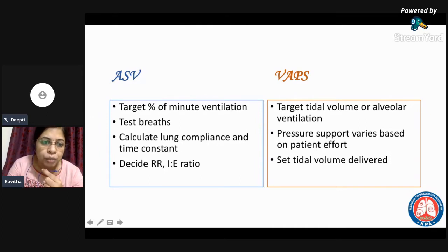But in a patient where you need to make sure that the patient is getting enough tidal volume, which are these conditions, we'll see in the future slides. But in a patient where you want to ascertain that a particular tidal volume is being rendered to the patient, these newer modalities may be of use. So in ASV, the target is the percentage of minute ventilation.